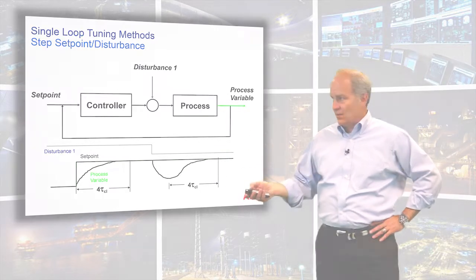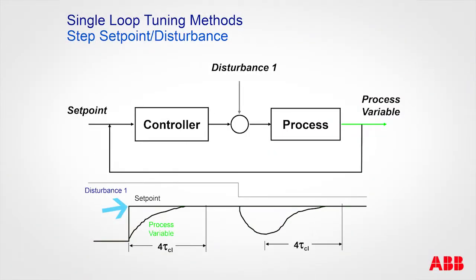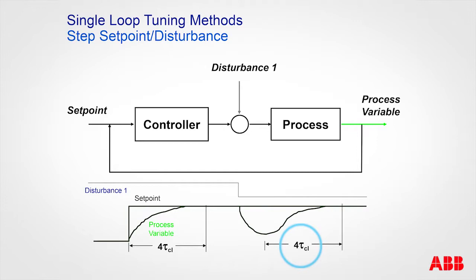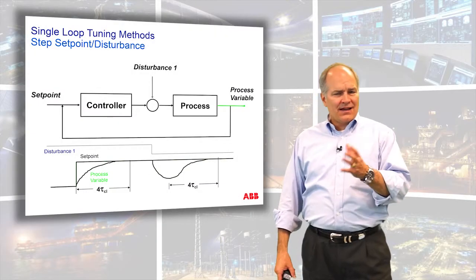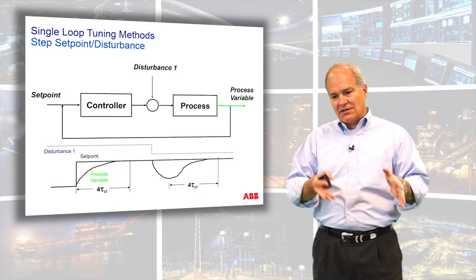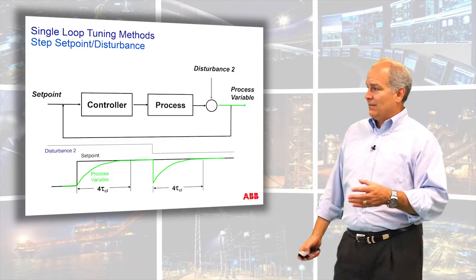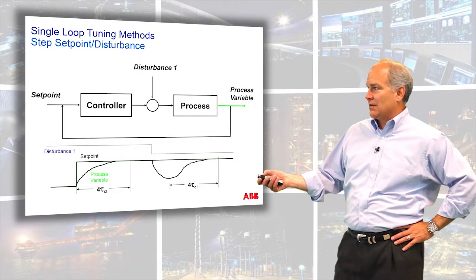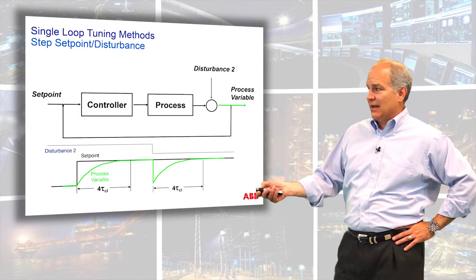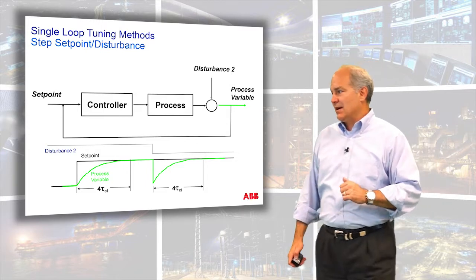Here's an example we've talked about: where I change the set point, you can see the measurement. If we assume a first order process, it's going to take roughly four closed loop time constants for the measurement to settle out at the set point. Similarly, a disturbance that goes through the process takes four time constants to come back. So if I have a step change or a disturbance change, it's going to take four time constants to recover.